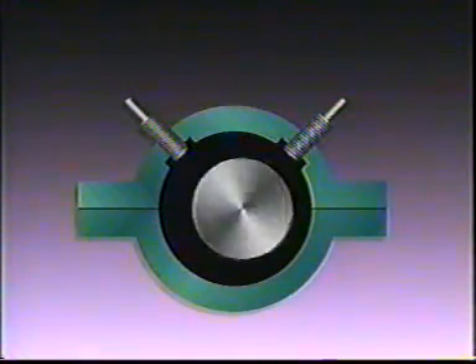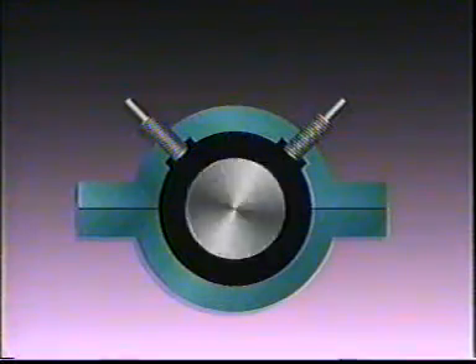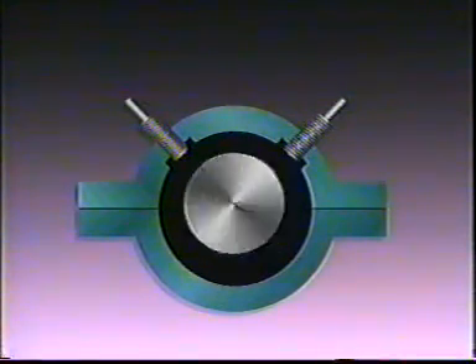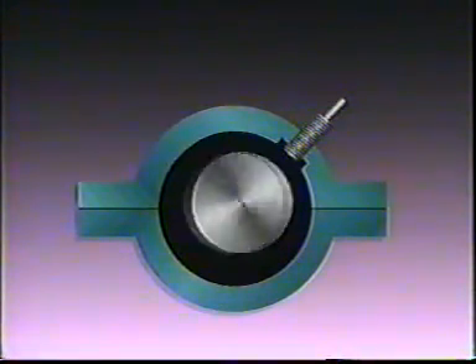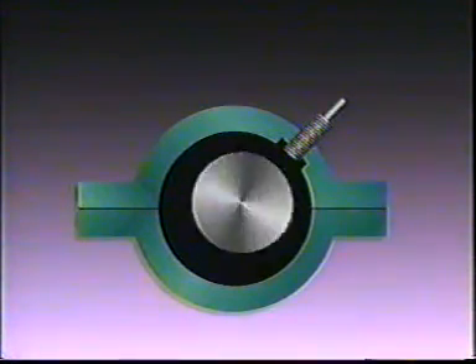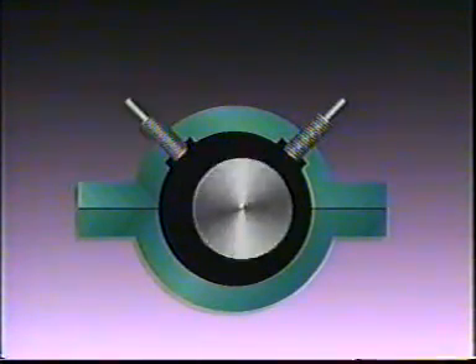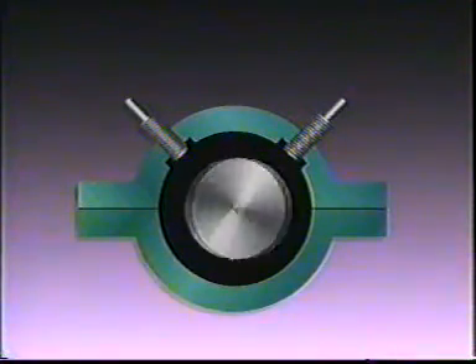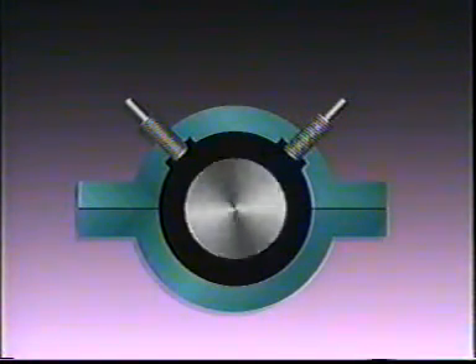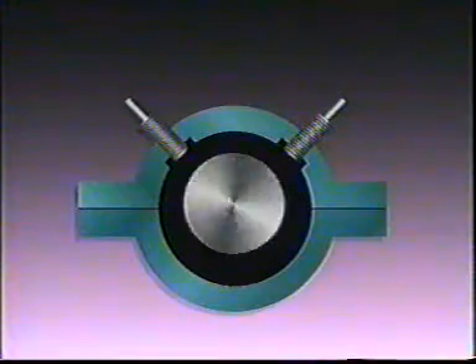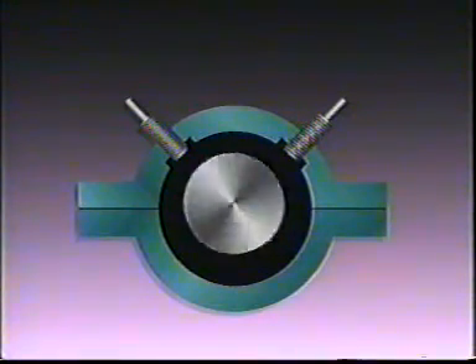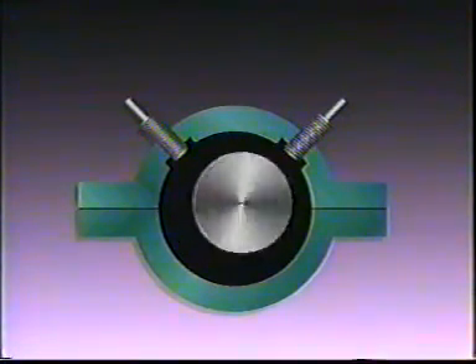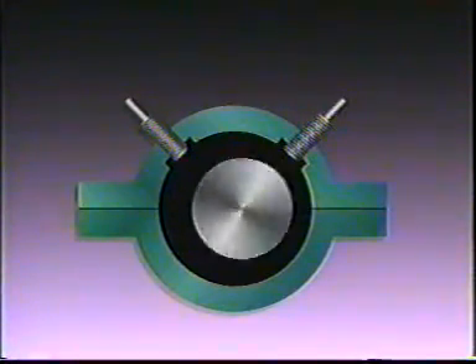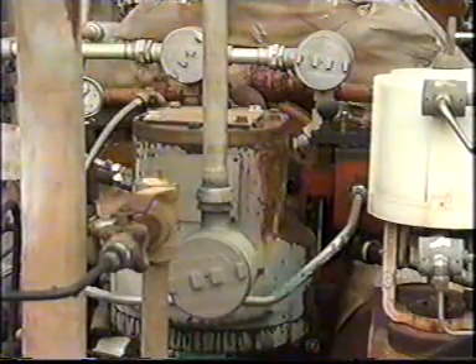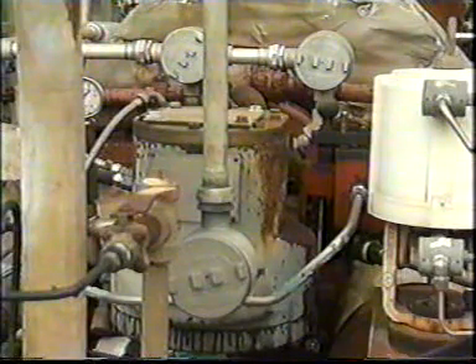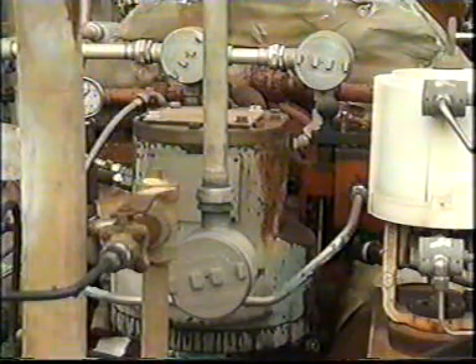Watch this shaft spinning inside its motor. Notice the shaft position changing inside the bearing as it spins. A single sensor will only show the displacement along one axis. As long as the 2 sensors are mounted 90 degrees apart, they will show the shaft's centerline relative position. By processing these 2 signals, we can find the radial or rolling displacement inside the bearing. For a complete picture of bearing performance, all 3 measurements need to be analyzed.